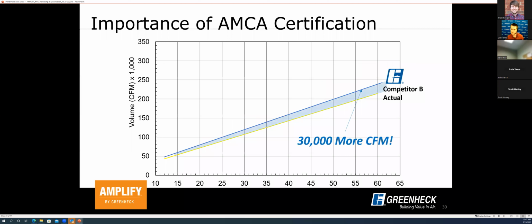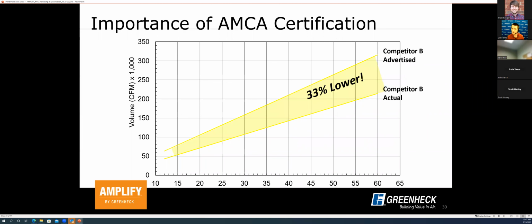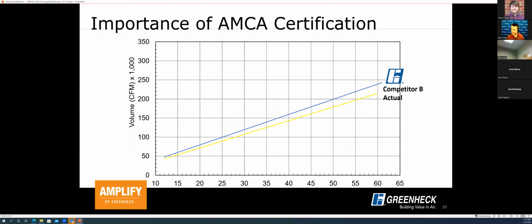Just for reference, here's a comparison of a Greenheck product to a particular competitor's product, as tested according to the same standard. When you look at the original advertised numbers, the Greenheck product looks like it performs to a lower level. But when we test them both to AMCA 230, there's quite a bit more airflow out of our fan compared to this particular manufacturer's fan.